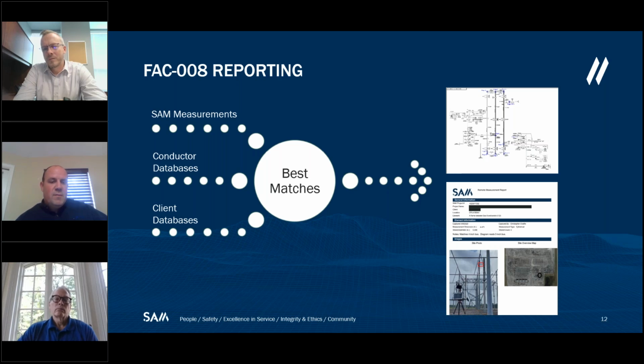And then we take our measurements and we look at conductor databases from Southwire or Alcoa, client databases like their bill of materials, what's written on the 3-line, and we find the best match. These are all the things that are within 0.03 of an inch and plus or minus one strand of the outer strand count that we calculate.